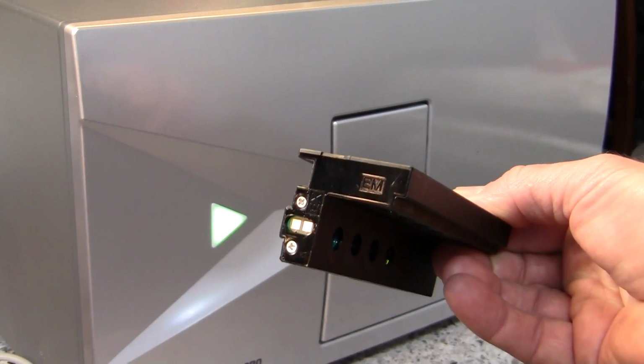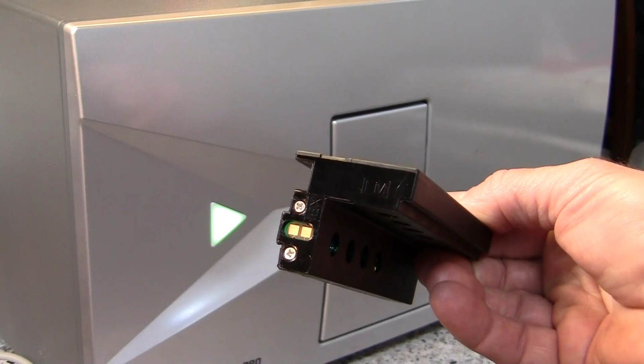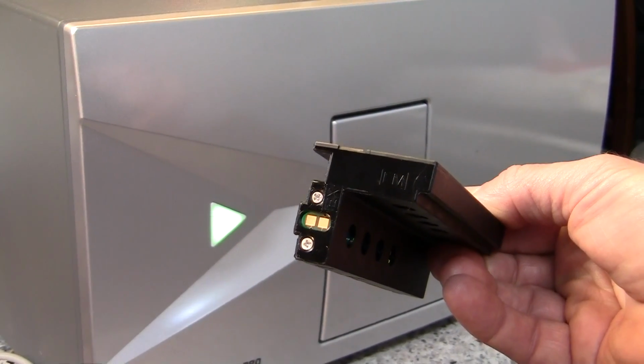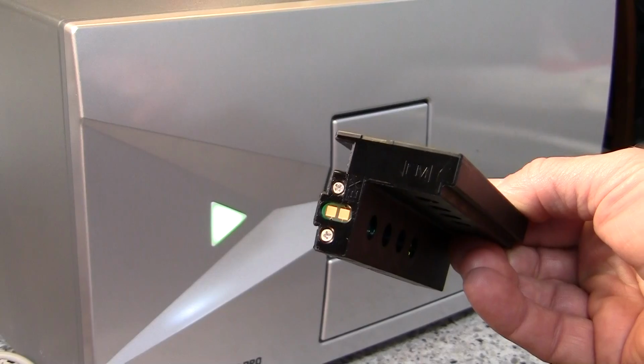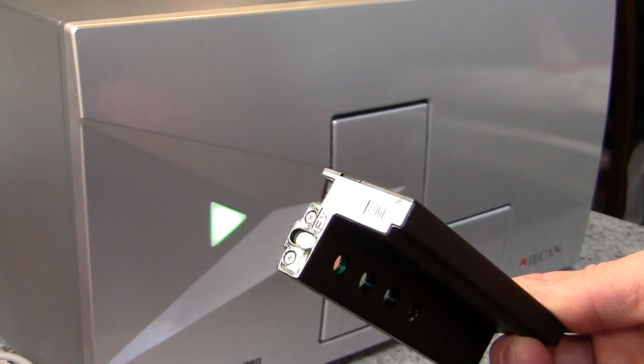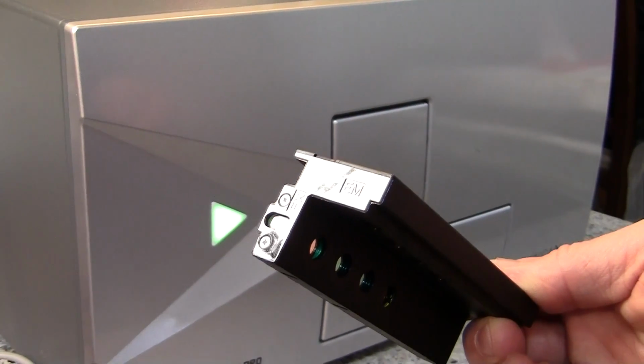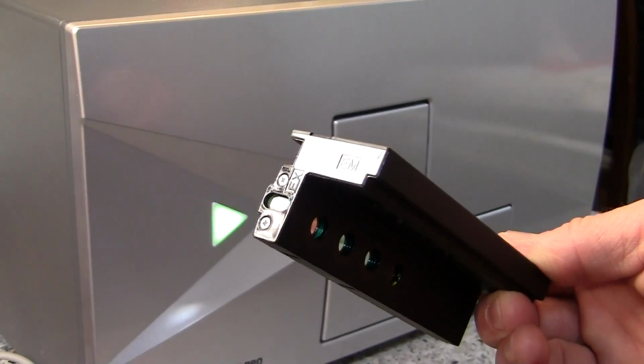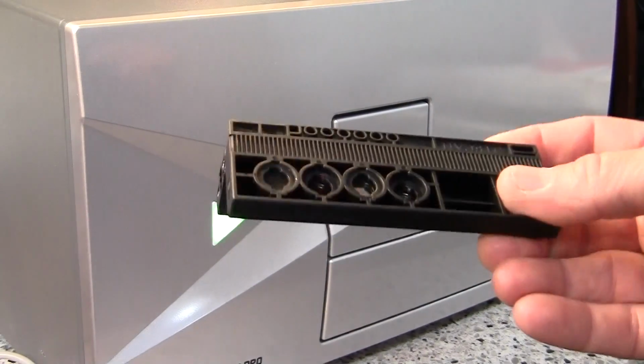There is a small memory chip located on the front end of the filter holder that is used to record what filters are in which position. The memory chip allows users to have multiple holders with different combinations of filters on them.